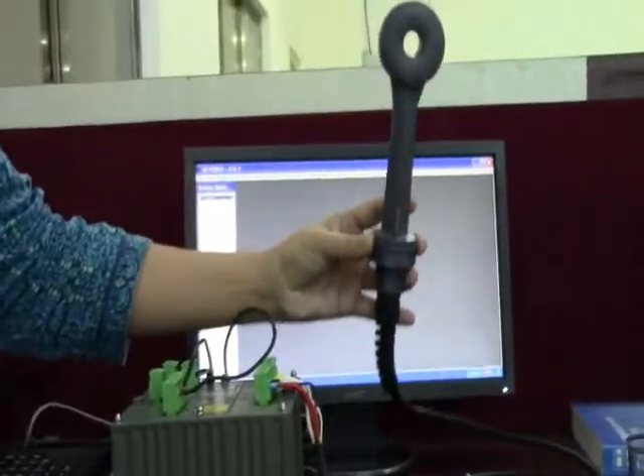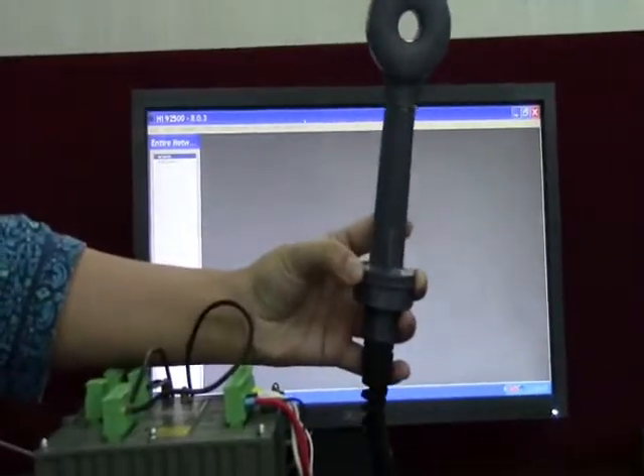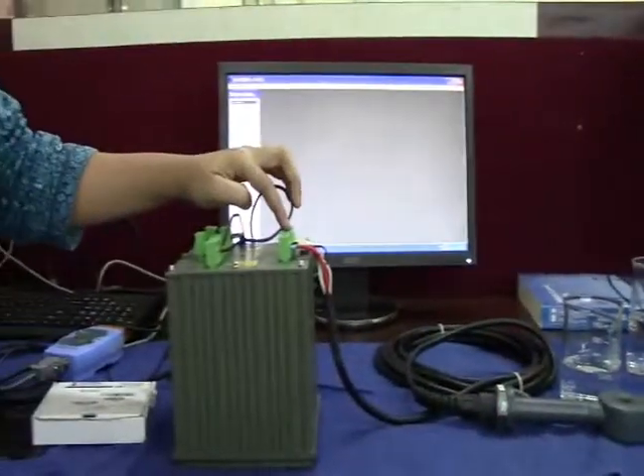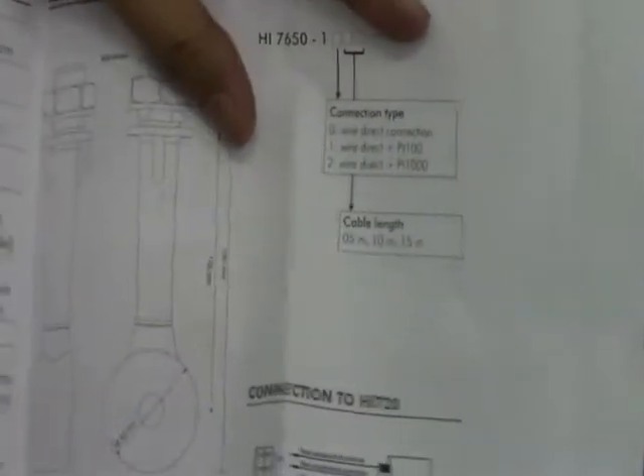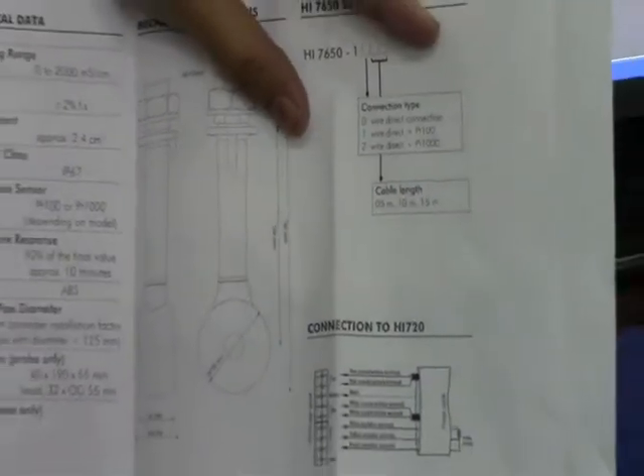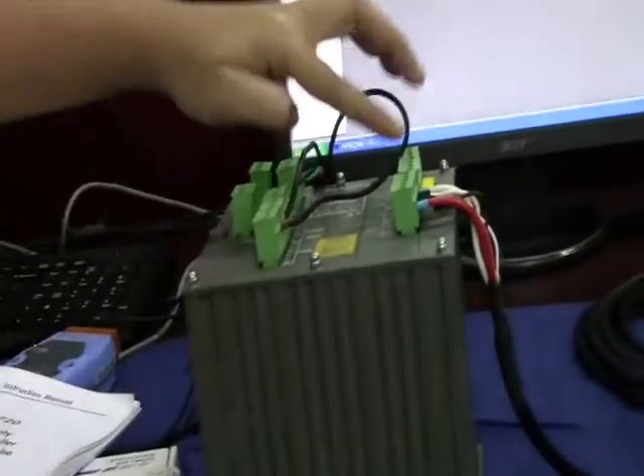HI 7650 is a conductivity inductive toroidal probe which is connected to the controller. It has color-coded wires. The connection has been clearly mentioned in the manual which is provided with the probe. The connections have been made as per the color code.